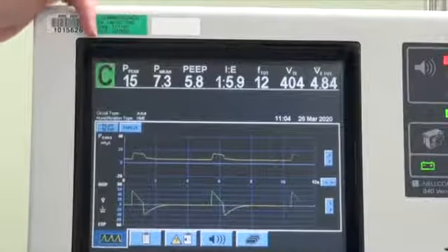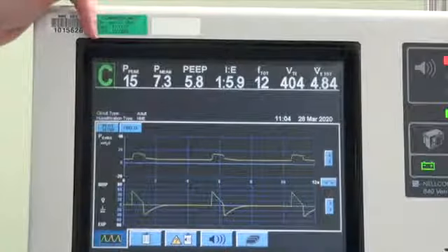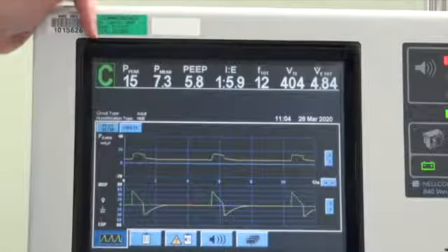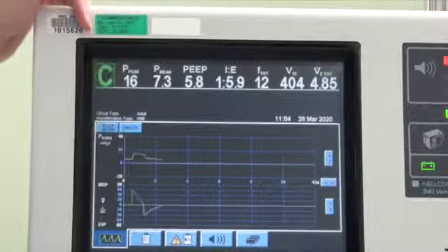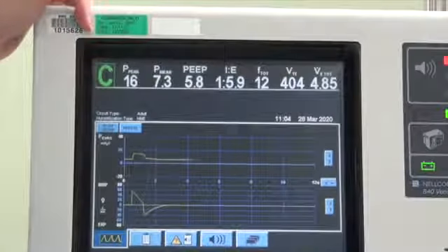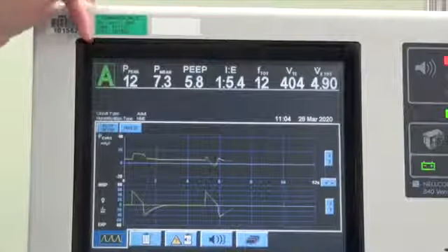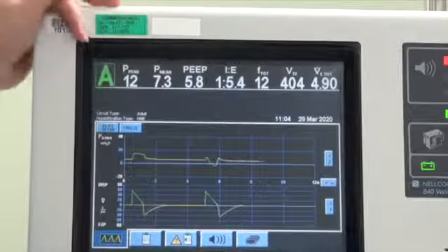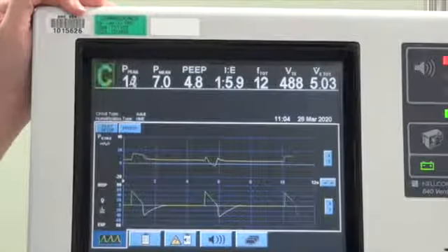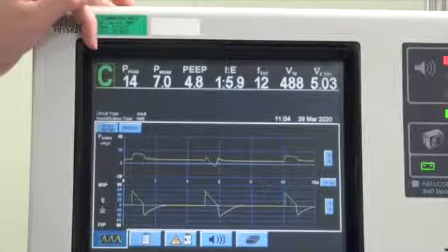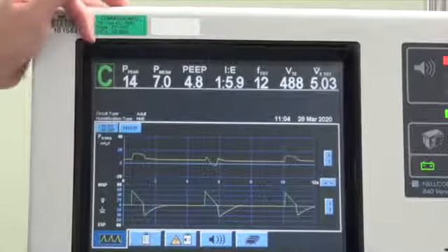Basically, this means that the tidal breath that is delivered to the patient is actually initiated by the ventilator and not the patient. If this is a spontaneous effort, you will see that it turns to A, which means that this is an assisted breath triggered by the patient and fully supported by the ventilator.